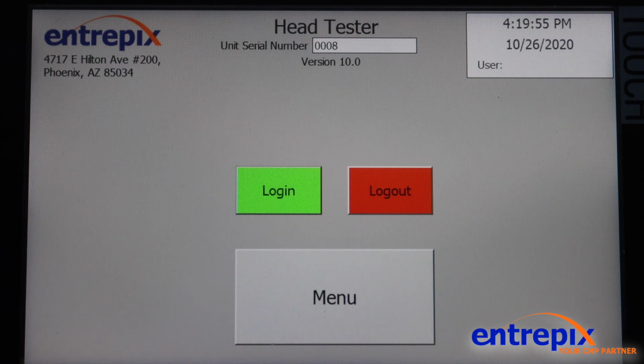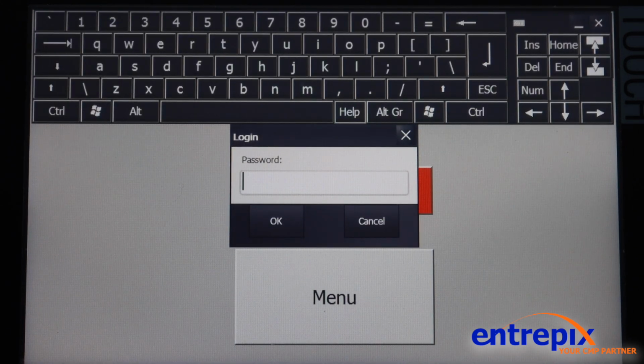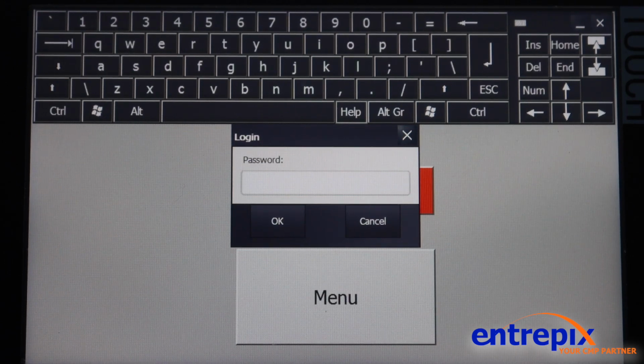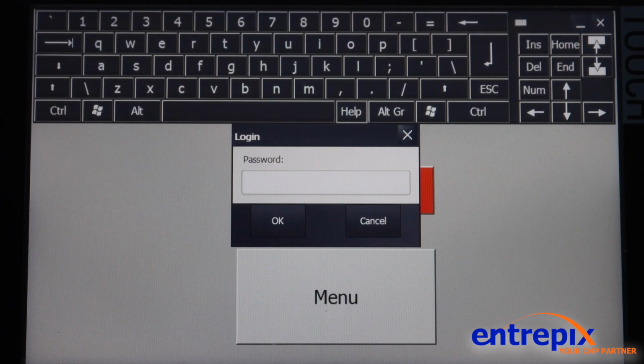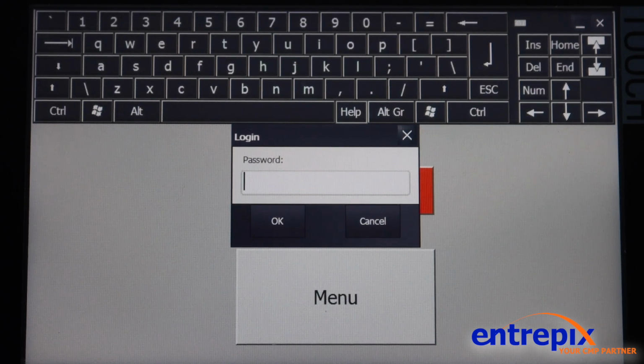There are three login security layers: Administrator, User 1, and User 2. The administrator can perform all possible functions for the head tester, including security passphrase modification, offset modification for calibration purposes, as well as incrementally and fully automated testing step by step while in semi-automation mode. User 2 will have the same capabilities, but without permission to change login security codes. User 1 may not change security information nor run test sequences in semi-auto mode, and is restricted from the manual operation screens.